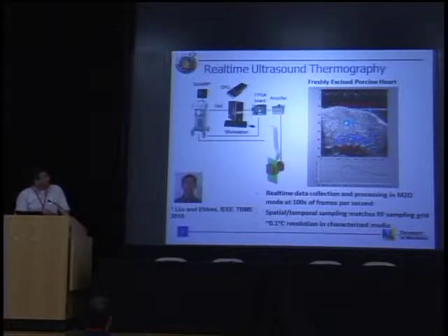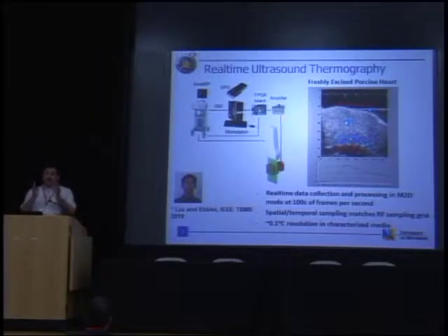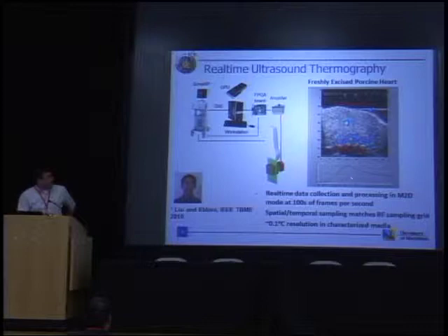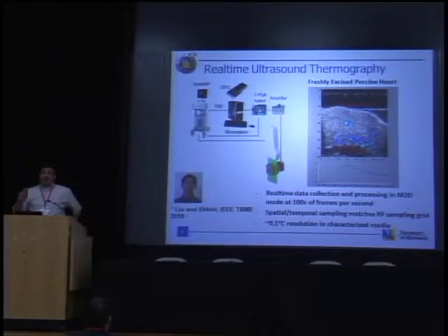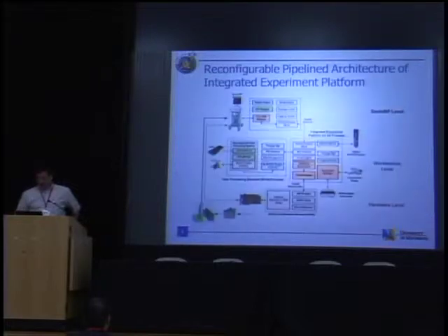We call this M2D. As Dr. Tantar explained, if you want to improve the frame rate, you can reduce the number of lines with conventional ultrasound. That's exactly what we do. But the idea is that we want to work at sufficiently high frame rates, in the 100 frames per second range, to achieve the fine spatial and temporal resolution that allows us to do some of the signal processing that's needed to extract the temperature data.